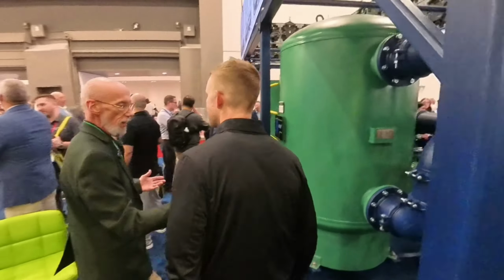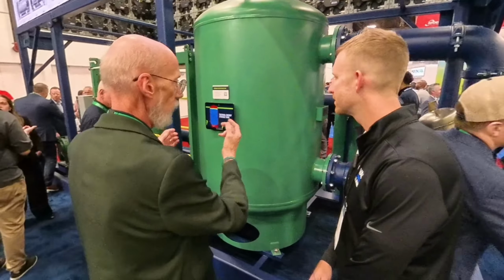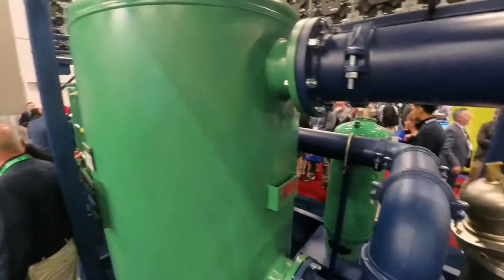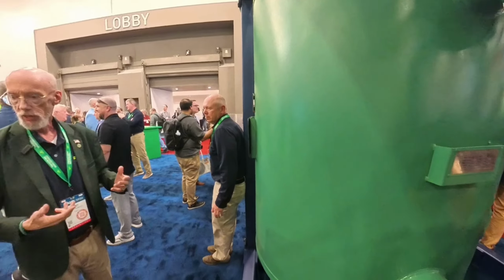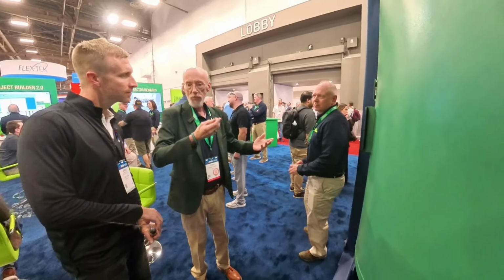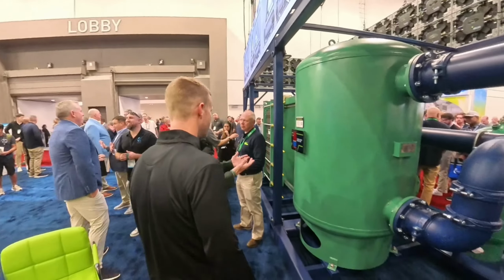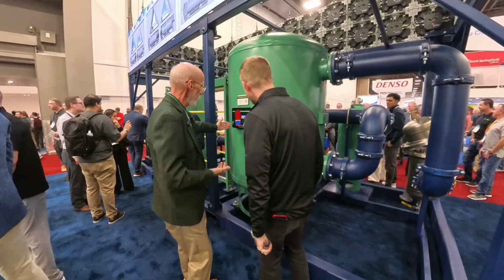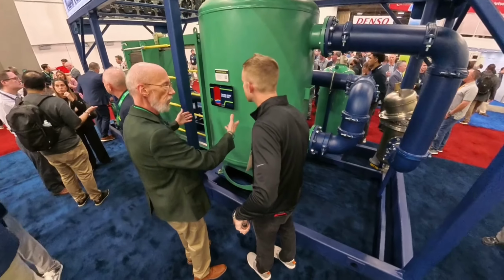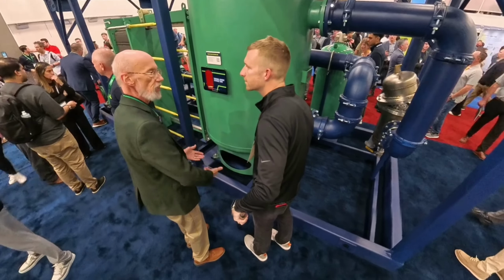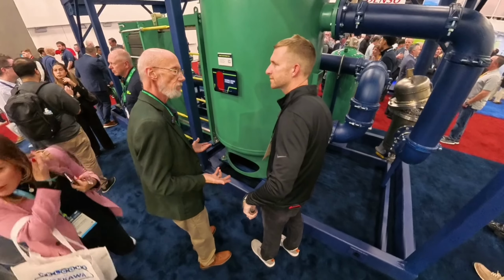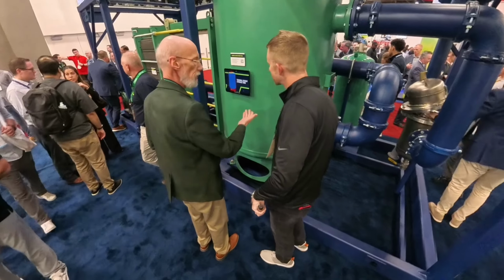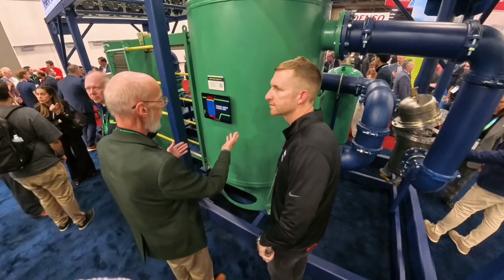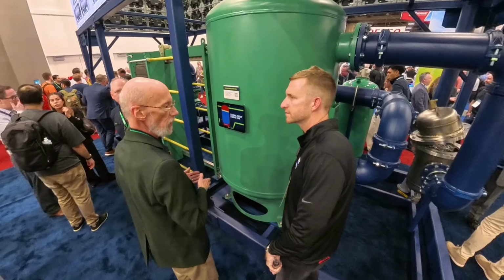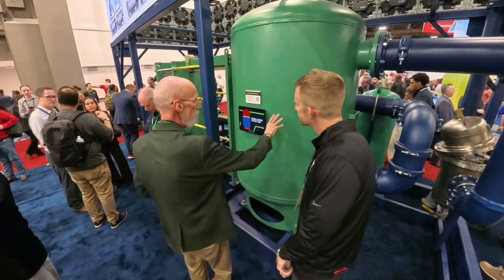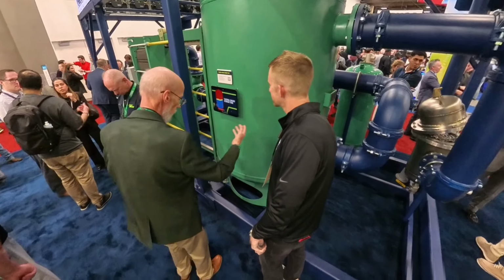So we start here, and at this point we have a thermal energy storage tank. In the data center world, if they have a power outage, the chillers go offline, but the pumps can recycle really quickly - the chillers can't. So how do they maintain chilled water? This thermal energy storage tank provides a mass of chilled water for 15 to 20 minutes until the chillers can cycle back up again and keep the cooling going in a data center. We have the ability to do computational fluid dynamics and calculate the exact performance and verify it before it ever gets built. We build these in our plant in Fall River, Massachusetts, so we've mounted one here.